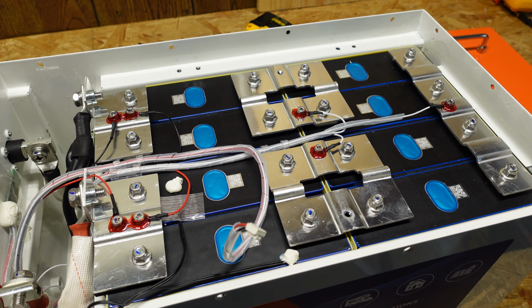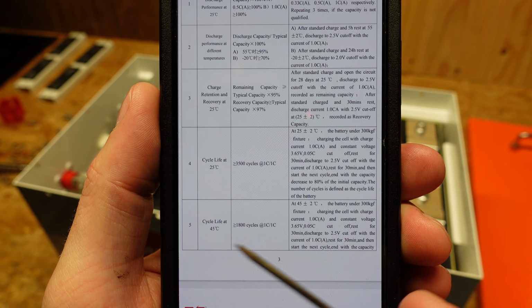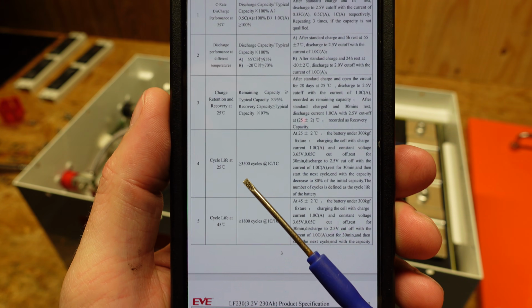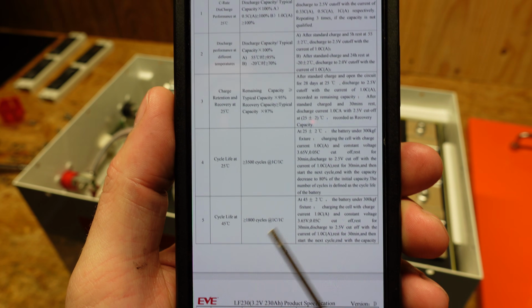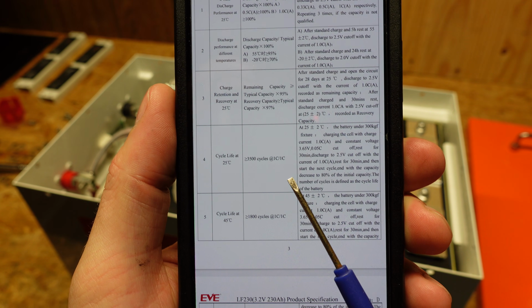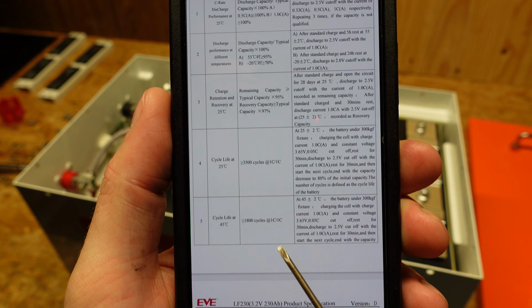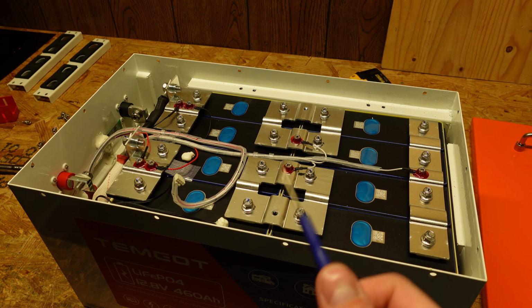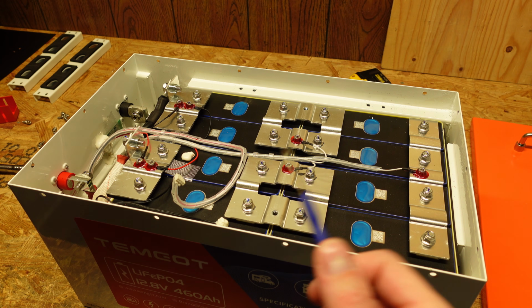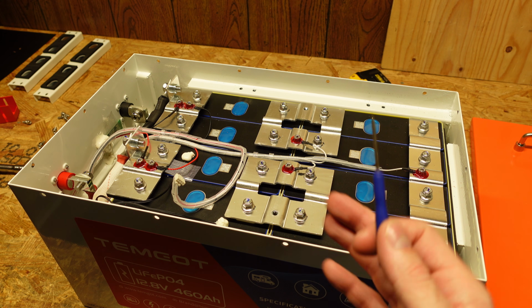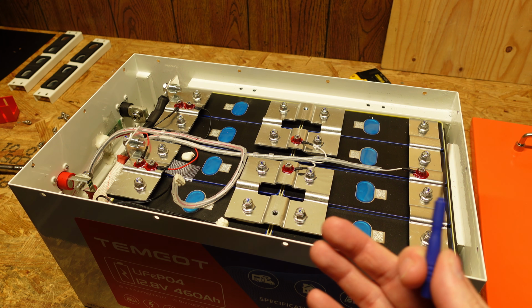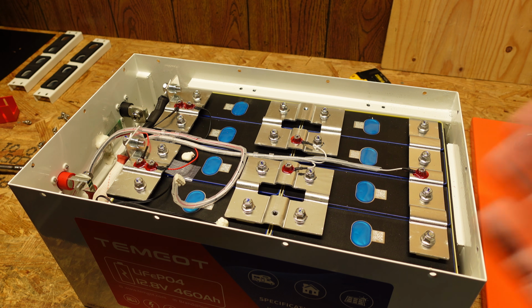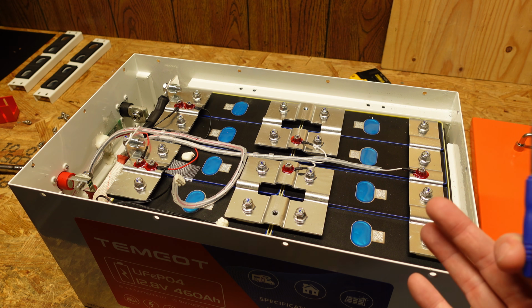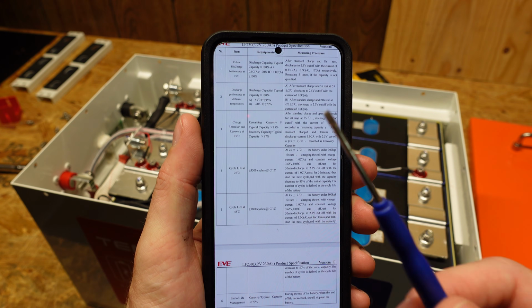So let's take a look at the datasheet. According to the datasheet that I found, the LF230 is rated for 3,500 cycles or more at a 1C charge-discharge rate at a 25 degrees Celsius environmental temperature. So these should be good for significantly more than 2,000 cycles. I don't know why that graph in the manual says 2,000 cycles. I suspect it's a very generic chart that they've simply copy and pasted from another manual, but I can't be certain of that. I can only tell you what the manual says and what I see in the specification sheet for the LF230s.